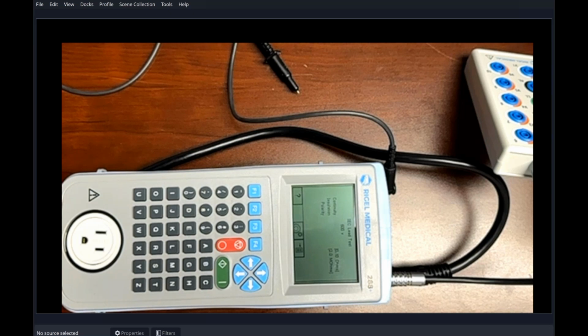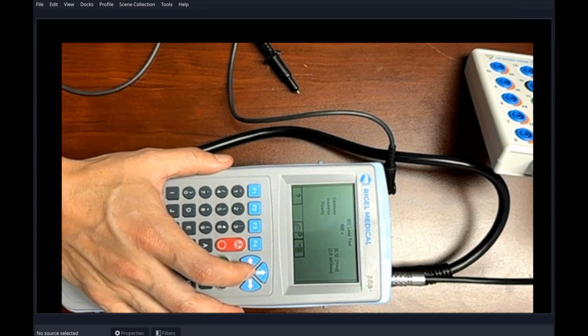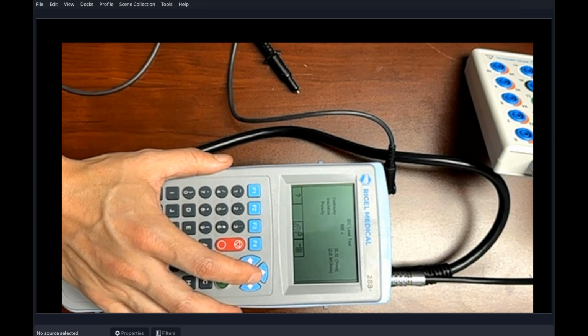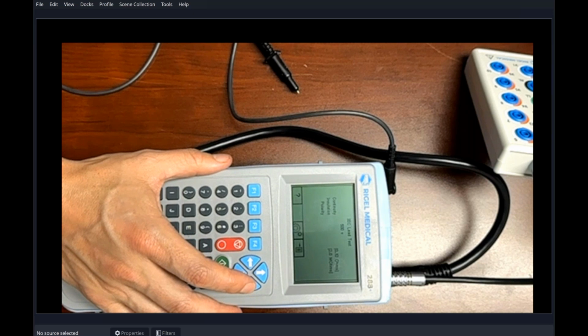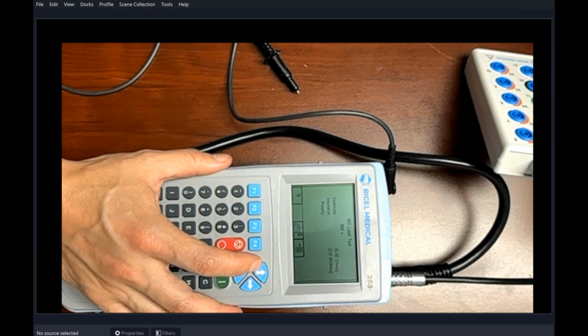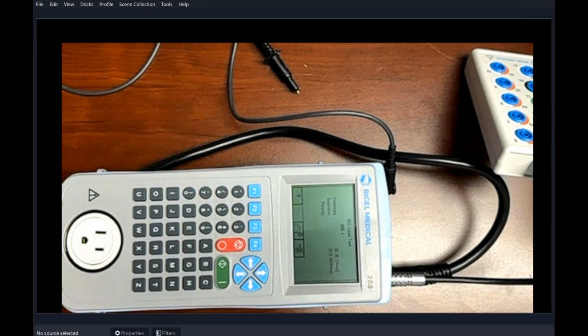So then it's looking at additional features that come with the device. Is Bluetooth needed, for example? Do you need to export your data from the safety analyzer? Does it have automated test sequences? One of the simplest ways of streamlining workflows is by having a test that's already pre-programmed. You don't need to input the test manually. And also the key benefit of having automated testing is that the results are then recorded, and you've got traceability of measurement there as well. If results are written down, or if it's just stated as a pass or fail, then you don't have that true traceability that you get with something that's automated.